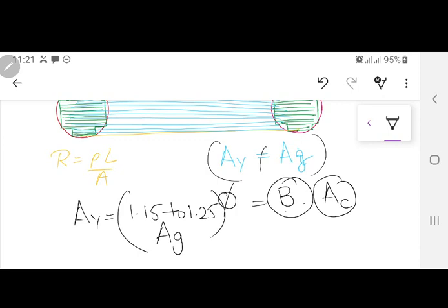So that losses inside the yoke are small. और हम यहाँ क्यों बढ़ा सकते हैं? Very good reason. We are not using a circular core. They are simple straight laminations. Nothing fancy about it. So the cost भी इतनी नहीं लगनी, wastage भी नहीं है. So it's better to increase the area by 15 to 25%, not more than that.